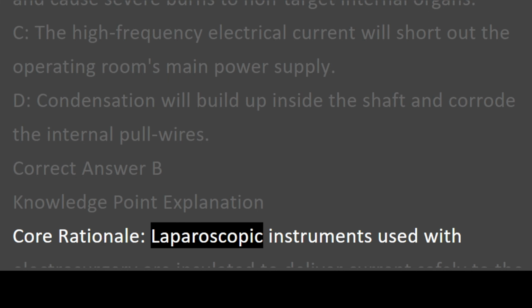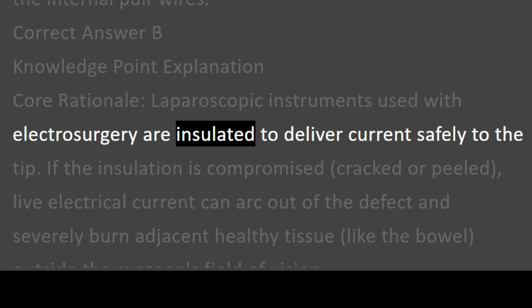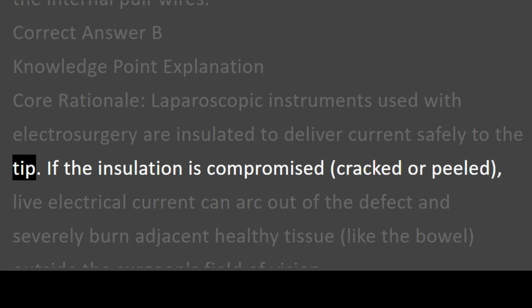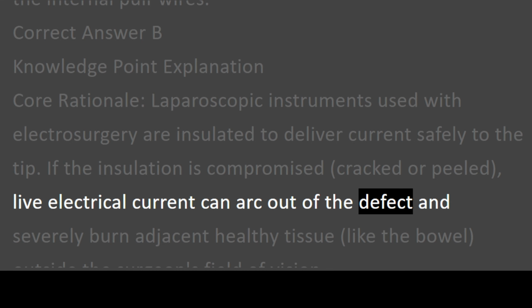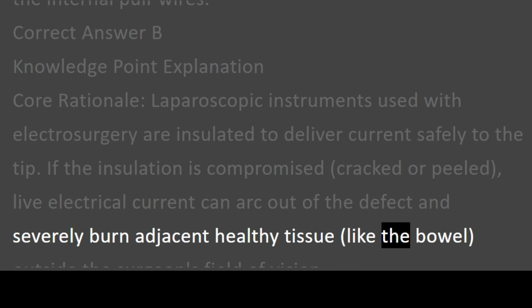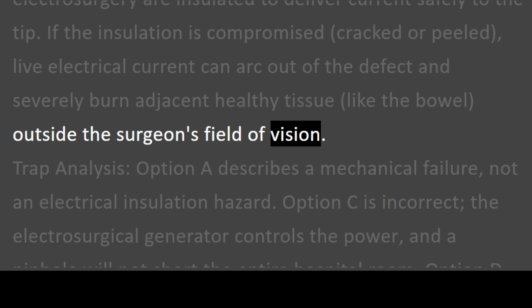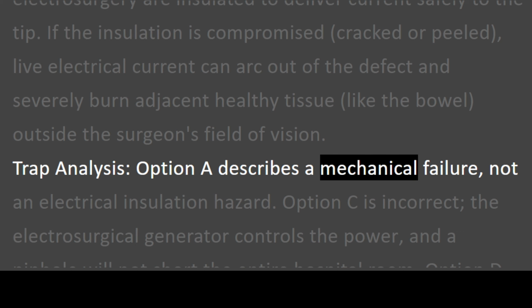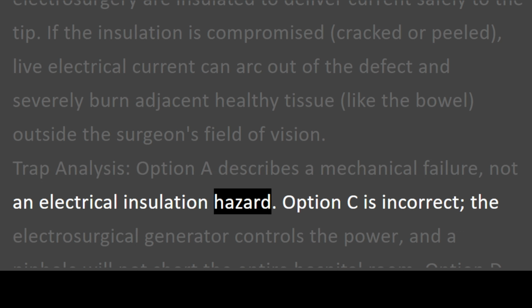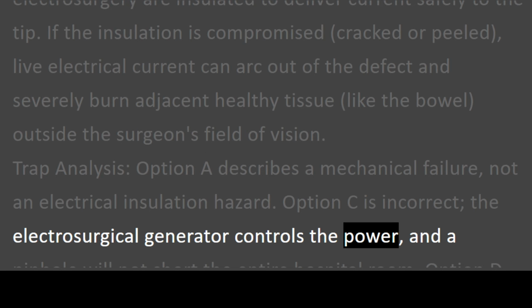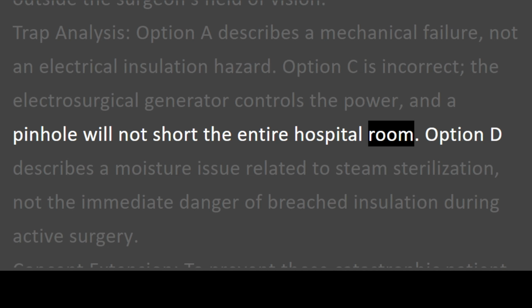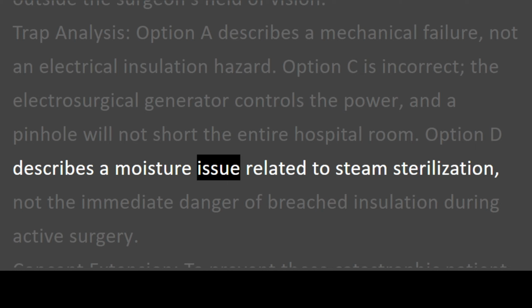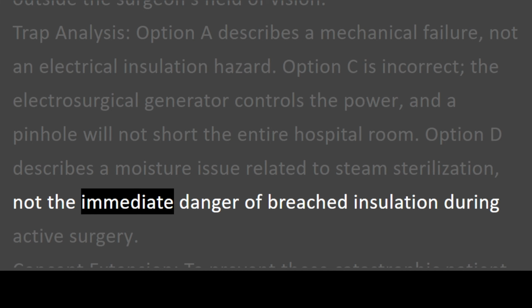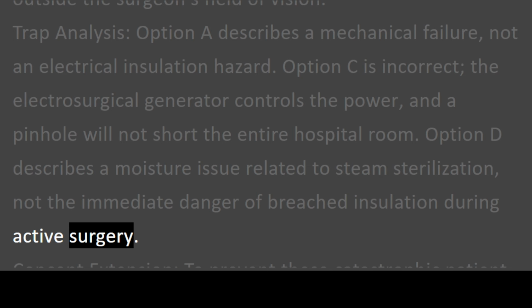Core rationale. Laparoscopic instruments used with electrosurgery are insulated to deliver current safely to the tip. If the insulation is compromised, cracked or peeled, live electrical current can arc out of the defect and severely burn adjacent healthy tissue, like the bowel, outside the surgeon's field of vision. Trap analysis. Option A describes a mechanical failure, not an electrical insulation hazard. Option C is incorrect. The electrosurgical generator controls the power, and a pinhole will not short the entire hospital room. Option D describes a moisture issue related to steam sterilization, not the immediate danger of breached insulation during active surgery.